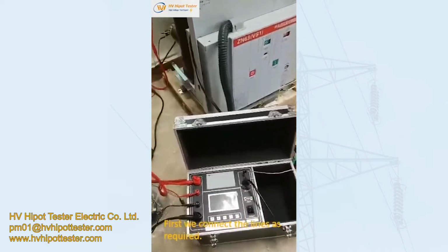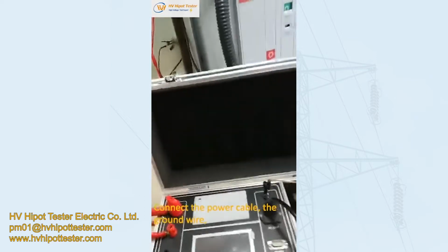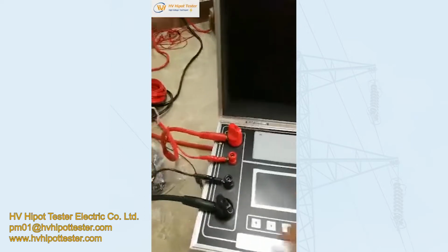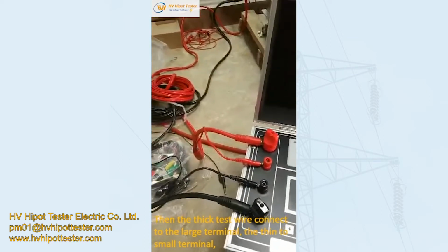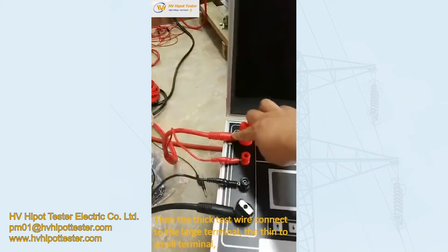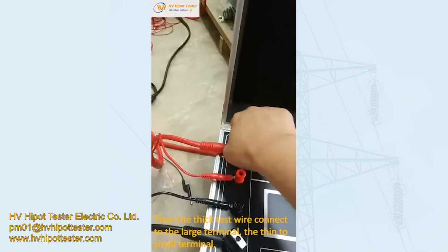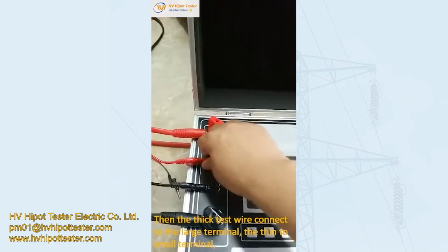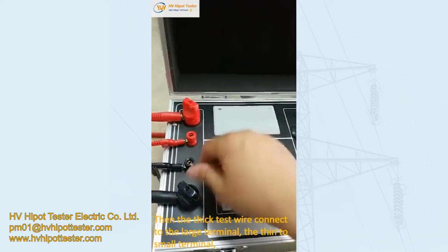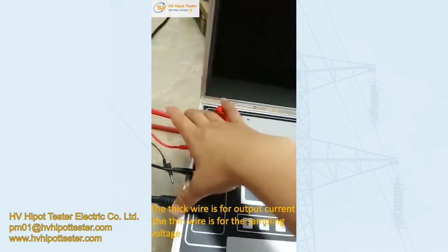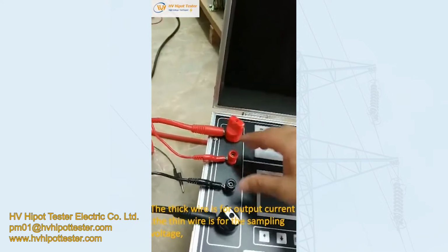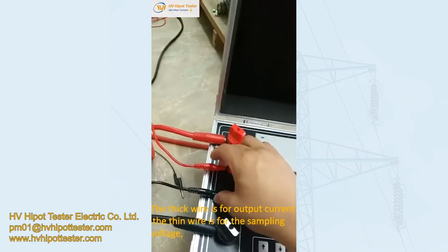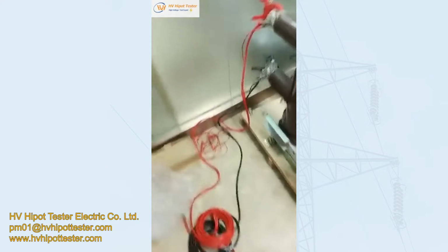First, we connect the lines as required. Connect the power cable and the ground wire. Then the thick test wire connects to the large terminal, and the thin wire connects to the small terminal. The thick wire is for output current, while the thin wire is for sampling voltage.